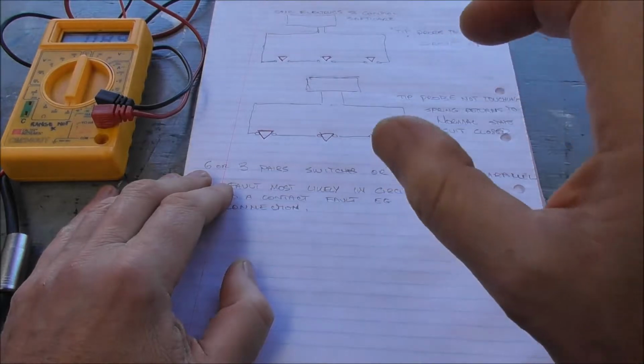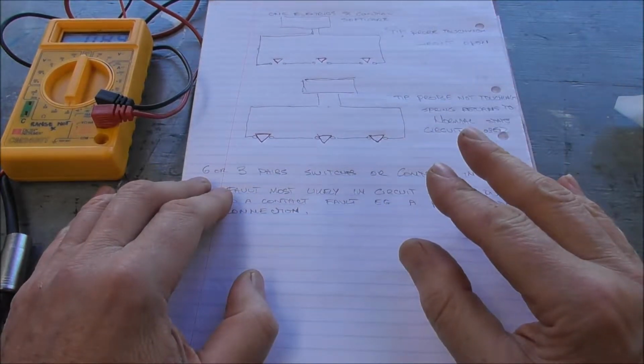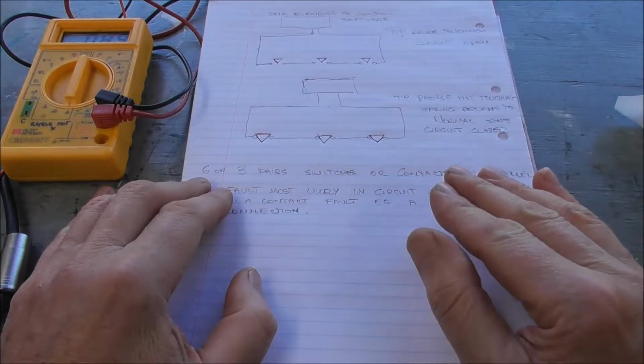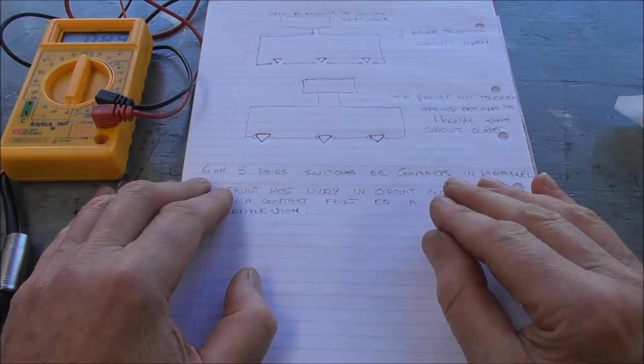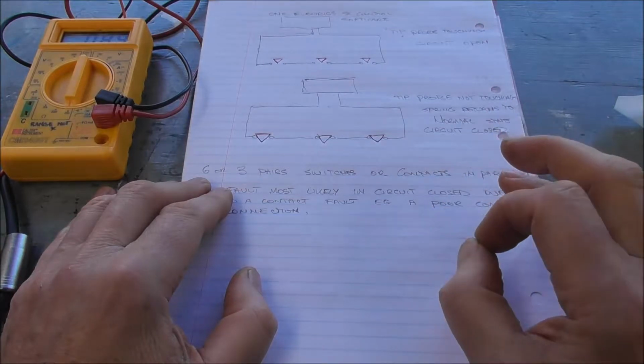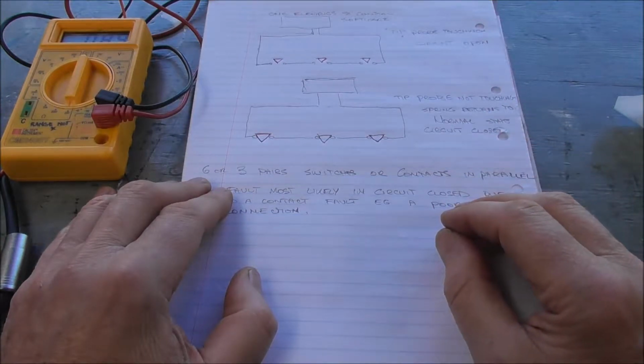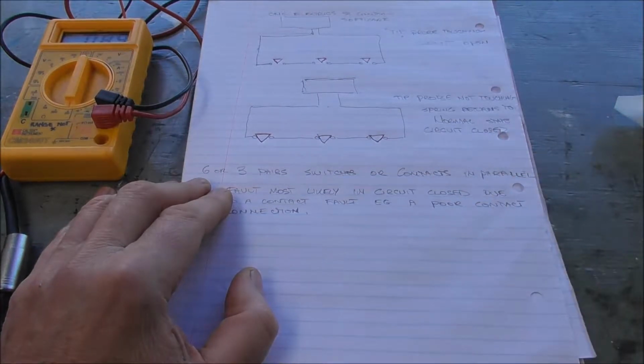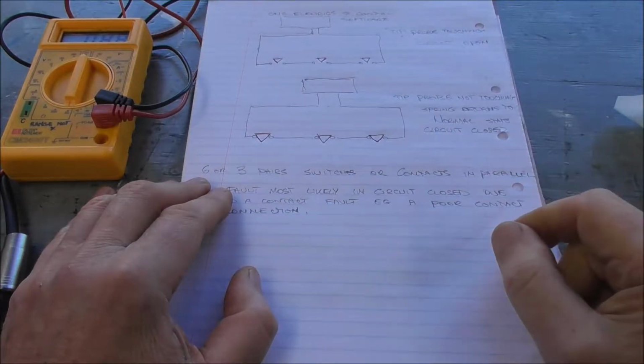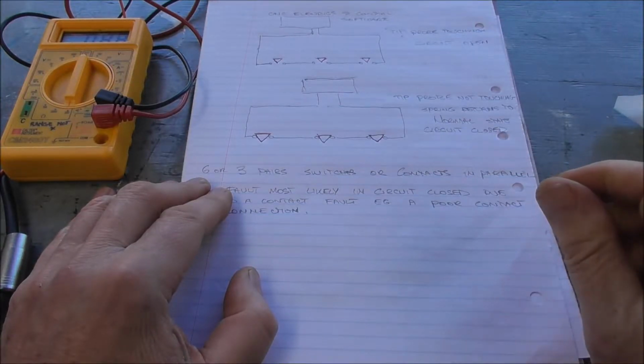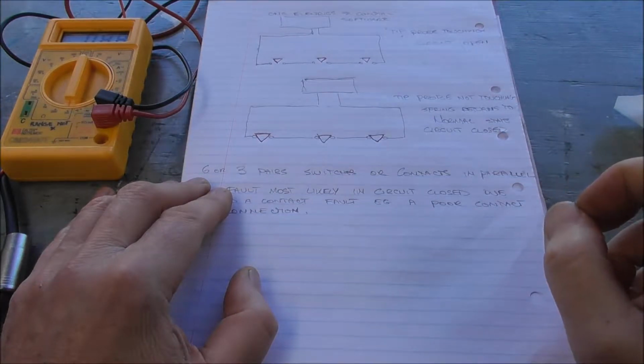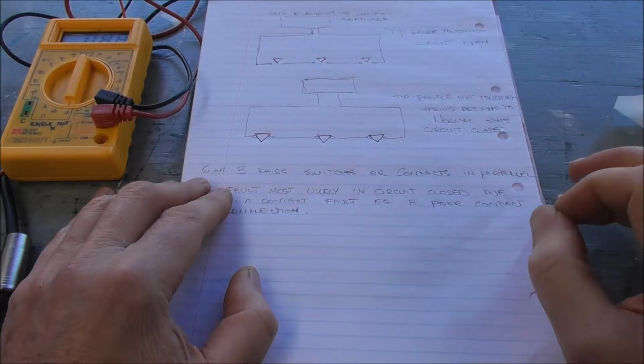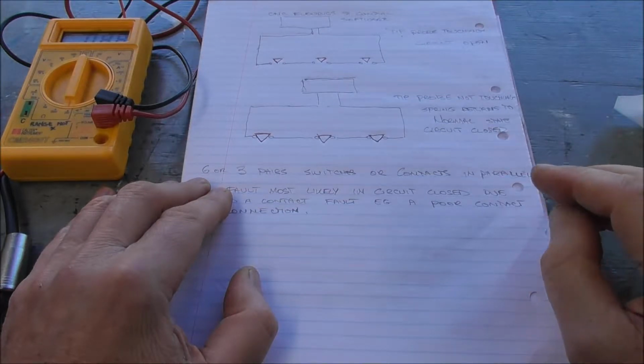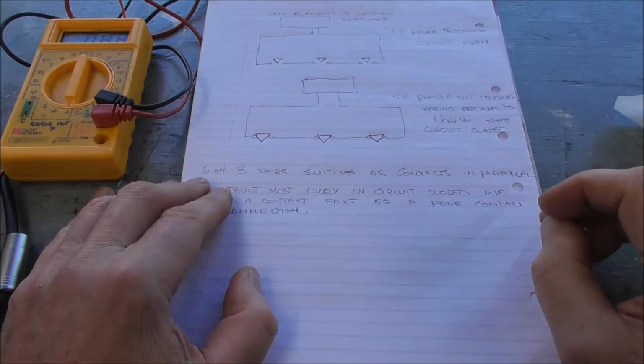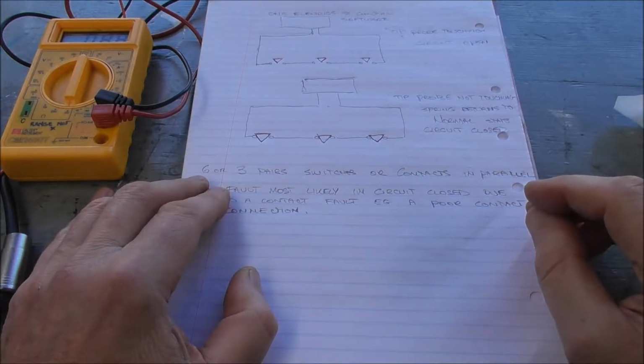Now, in addition to those most likely faults, there's also a possibility that a probe has or will develop a very rare situation where there's a short in the actual probe itself, so that when the probe should be open, the circuit should be open, it remains closed due to a short. Or it could be that there's a break in the electrical circuit, a dry solder joint or a faulty connection somewhere else in the circuit, and that would mean that when the circuit should be closed, it remains open. And I'll just go through a couple of ways you can check that.